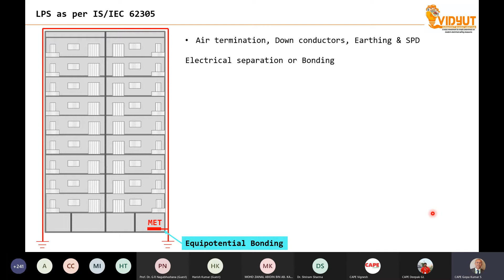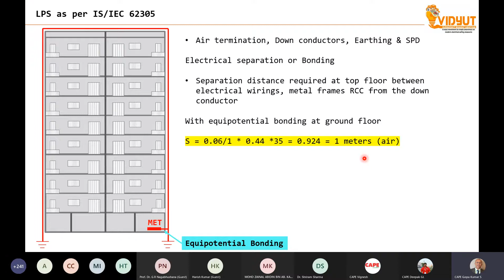Now, another important subject of this design is called electrical separation. Electrical separation means that once the lightning current flows through some of the conductive parts, there is a chance that nearby metallic parts could become dangerous because of a spark over. As a result, we are supposed to measure the separation distance, and the electrical apparatuses shall be kept a little bit away from the down conductor. Say, for example, now I am showing you a typical example with the calculation. Let us say, just as an example, 1 meter is the distance between the air terminal and the metallic parts.